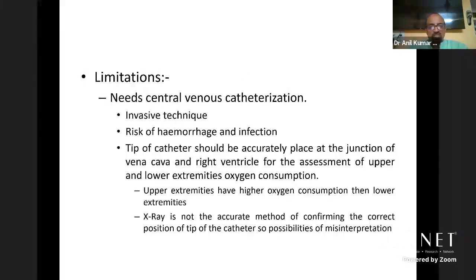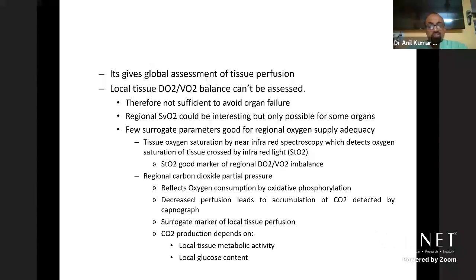But there are certain limitations, as we need central venous catheterization. That is a partially invasive technique, and there could be a risk of hemorrhage and infection. The tip of the catheter should be accurately placed at the junction of the vena cava and the right atrium. If the tip of the catheter is not placed correctly, there may be a little difference in the values. This SvO2 value gives a global assessment of tissue perfusion. It is not organ specific, and the local delivery of oxygen and the ratio between delivery and consumption for a local tissue or organ system cannot be assessed by this.